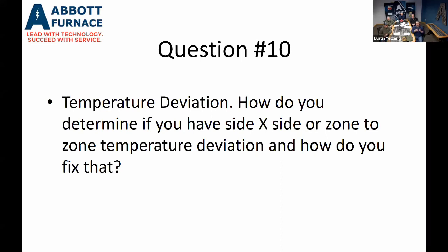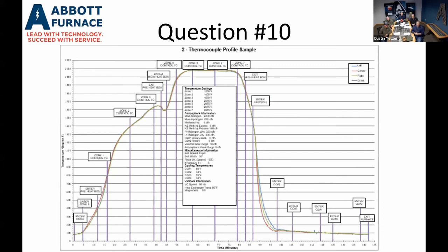Okay, so that's a two-part question. The one is side-by-side, and that is looking at the temperature inside the furnace, where the temperature profile would come into play. What we pulled up here is a typical 3 thermocouple profile that we would run on a furnace. We put thermocouples on the left side of the belt, the center of the belt, and the right side of the belt. We run these thermocouples the whole length of the furnace, taking temperature readings. That gives us a nice profile, or temperature uniformity survey, of what the furnace is seeing as far as temperature inside. This will determine if you have a side-to-side temperature deviation on your belt that your product would see.